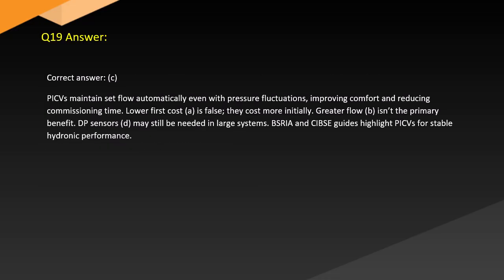Answer. Correct answer. C. PICVs maintain set flow automatically even with pressure fluctuations, improving comfort and reducing commissioning time. Low first cost, A, is false. They cost more initially. Greater flow, B, isn't the primary benefit. DP sensors, D, may still be needed in large systems. BSRIA and CIBSE guides highlight PICVs for stable hydronic performance.